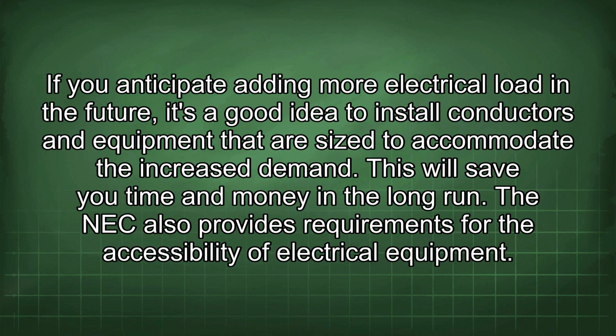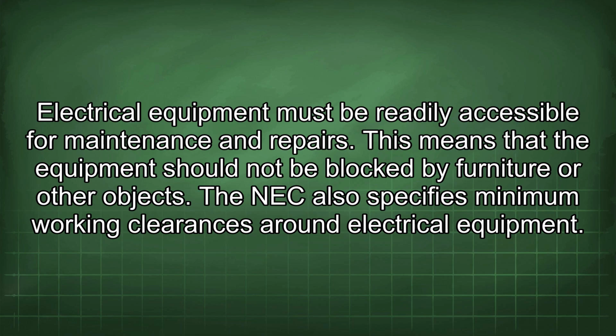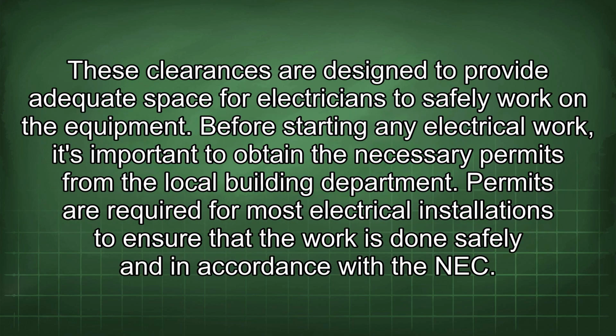The NEC also provides requirements for the accessibility of electrical equipment. Electrical equipment must be readily accessible for maintenance and repairs. This means that the equipment should not be blocked by furniture or other objects. The NEC also specifies minimum working clearances around electrical equipment. These clearances are designed to provide adequate space for electricians to safely work on the equipment.